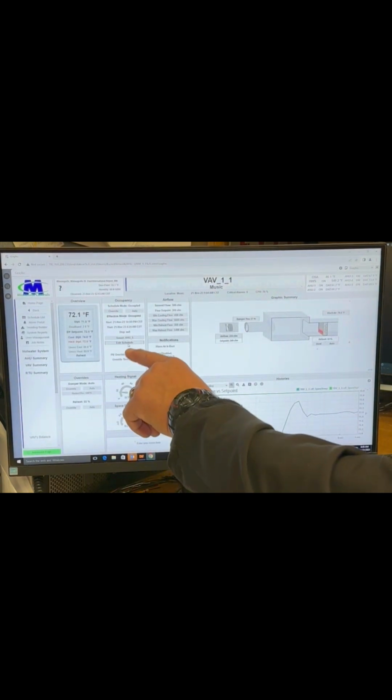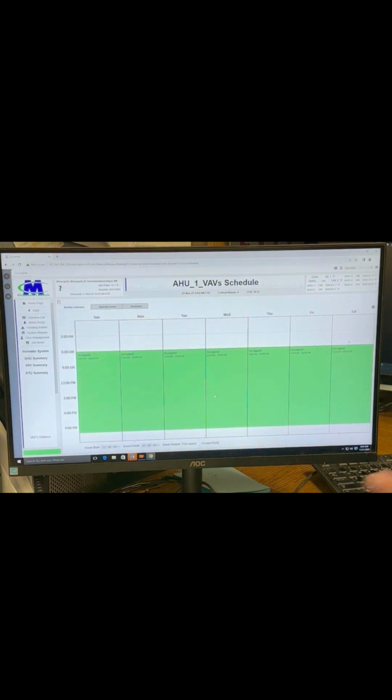Yeah, okay. And if I go to air handler, let's set it to air handler 5, click OK. So now this is going to update the AHU5 schedule. If I go there, now I'm going to edit the AHU5 schedule. It's going to change anything else that's tied to AHU5. Oh, okay. There shouldn't be, I don't even think anything's tied to it. But again, I don't want to change it.